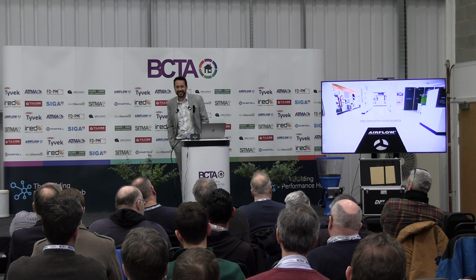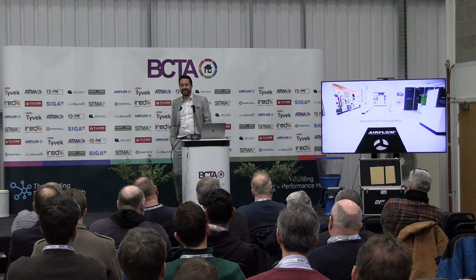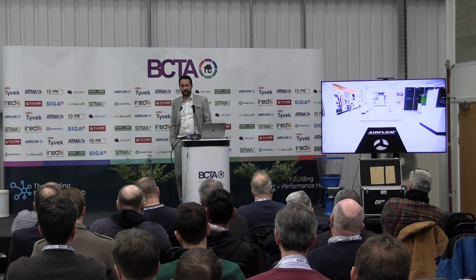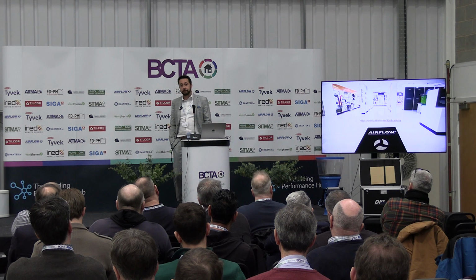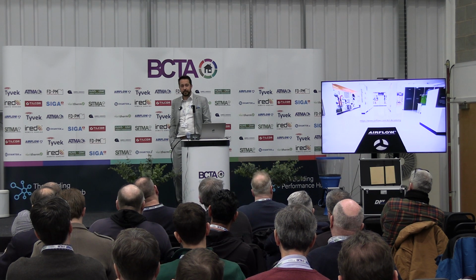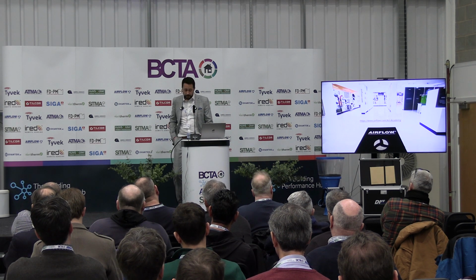Hi, Elliot. I know you didn't quite mention that air conditioning doesn't need ventilation under regulations, so it's not a choice of one or the other. Yeah. You need the ventilation regardless. Yes. The options are ventilation and air conditioning, or ventilation with cooling. Yeah. So, but I thought it might be worth you mentioning about the cool air recovery as well over the summer, because obviously if you cool the building down, you've got the cool air recovery from the MVHR the same way as you have warm air recovery. So you're reducing the load on the cooling system as well, and therefore that's where you get your efficiency saving over air conditioning. Yeah, exactly that.